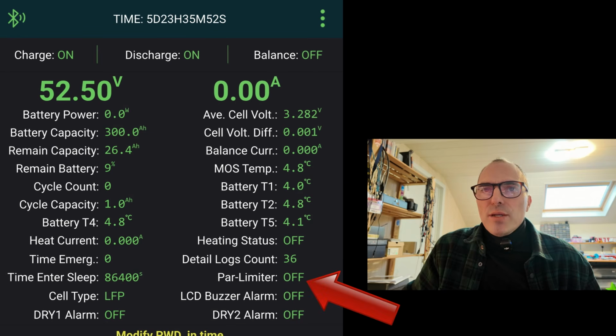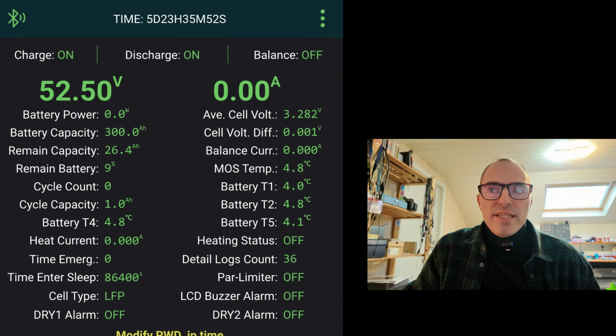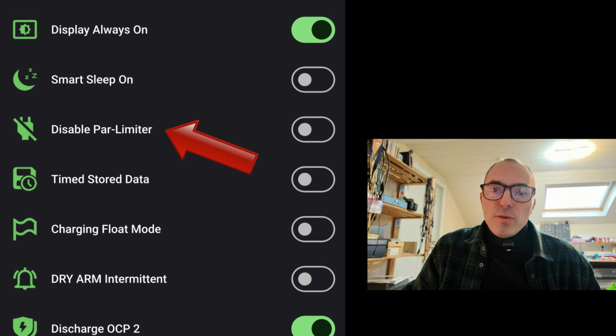PCL module is a module inside the BMS that's limiting the current between stacked boxes. If you add a new battery with a low state of charge and the first battery has a high state of charge, then high current can flow between battery boxes. Parallel current limiter, or PCL, will help to avoid this by limiting the current. This needs to be activated in the control menu as well.